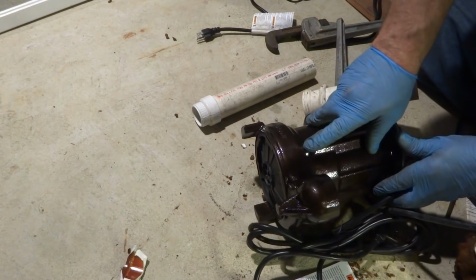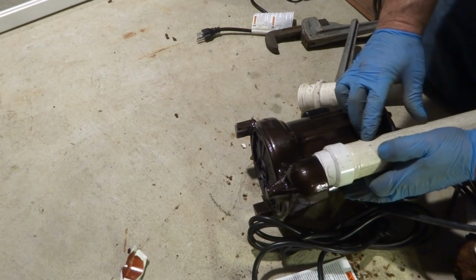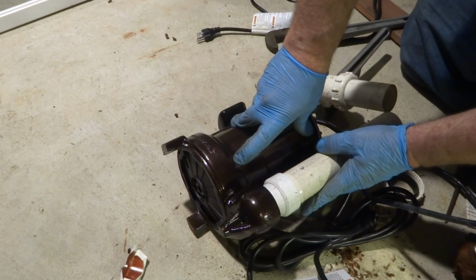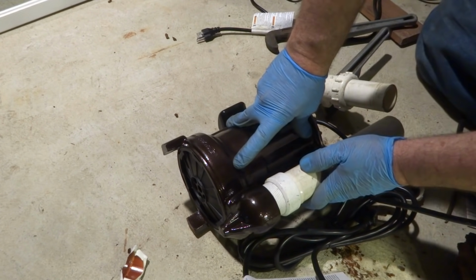And look at this pump. This pump don't have a hole drilled in it. Oh yeah, it does right there. See it? See the hole? So we're gonna have another hole that's up more. It's gonna have two holes there now. There's a hole there, so it don't get airbound, but they want you to put an extra one. It don't hurt if this ever gets rusted.